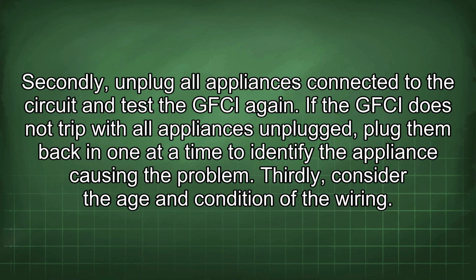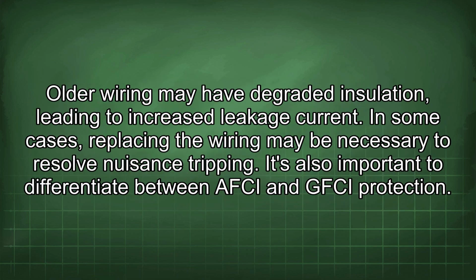Thirdly, consider the age and condition of the wiring. Older wiring may have degraded insulation, leading to increased leakage current. In some cases, replacing the wiring may be necessary to resolve nuisance tripping.